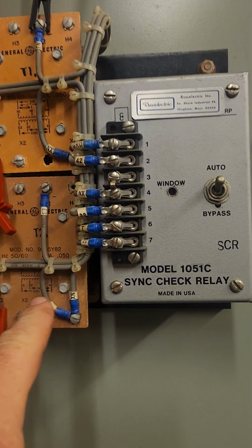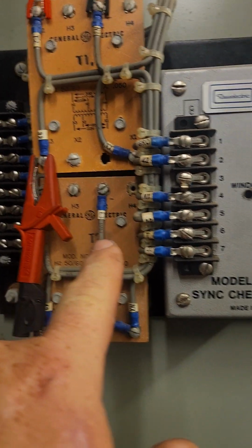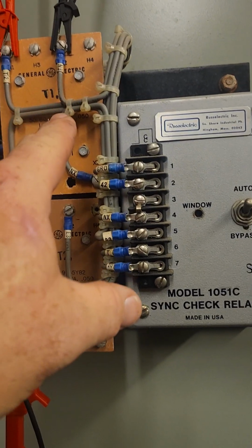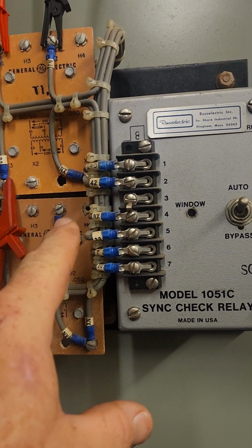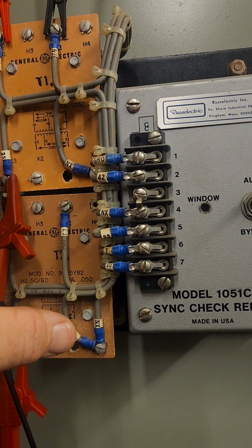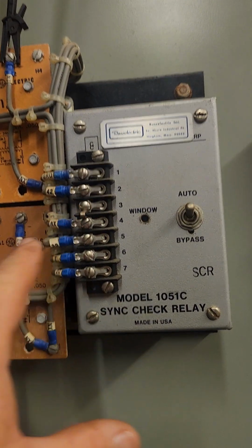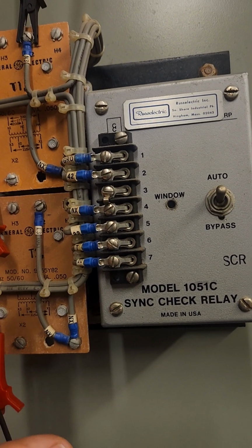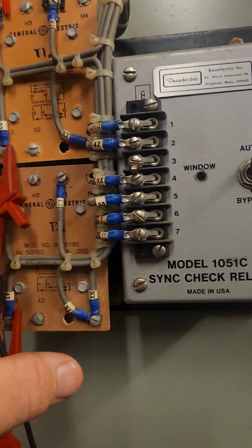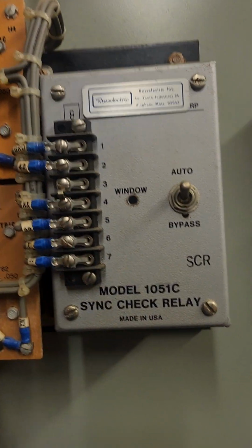So if you look at the load side of each relay, from normal and emergency, they're tied together, and then 32 of normal comes to the sync check relay, steps down from 208 to 120, and then 42 comes here, and then NX is bridged.